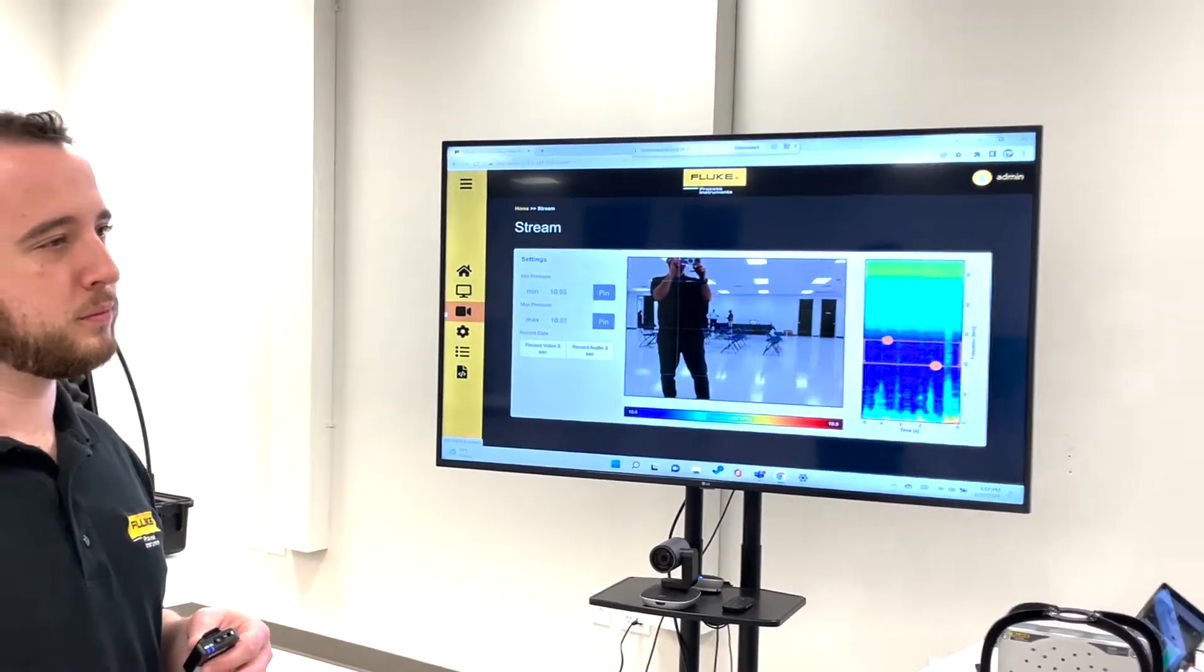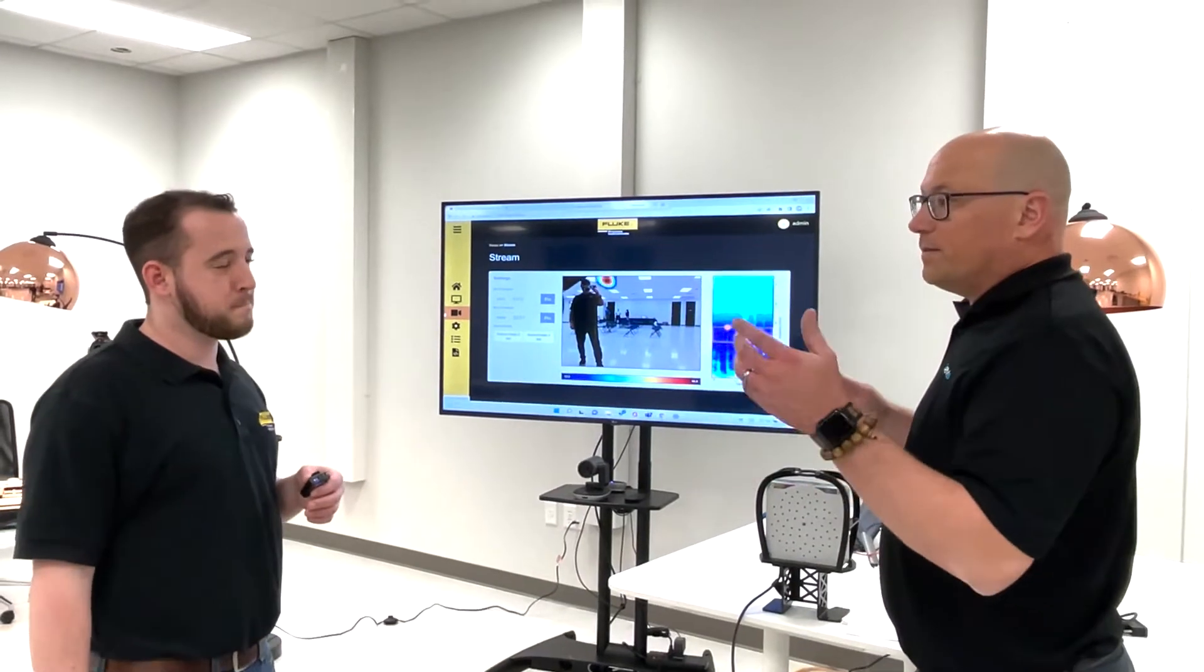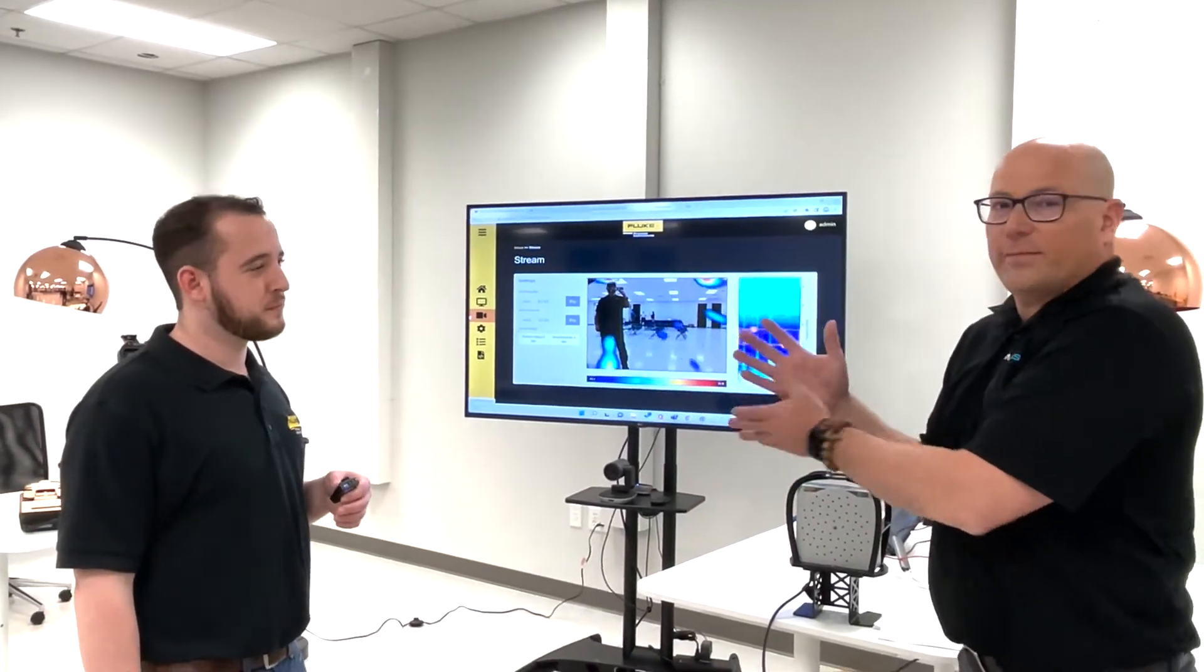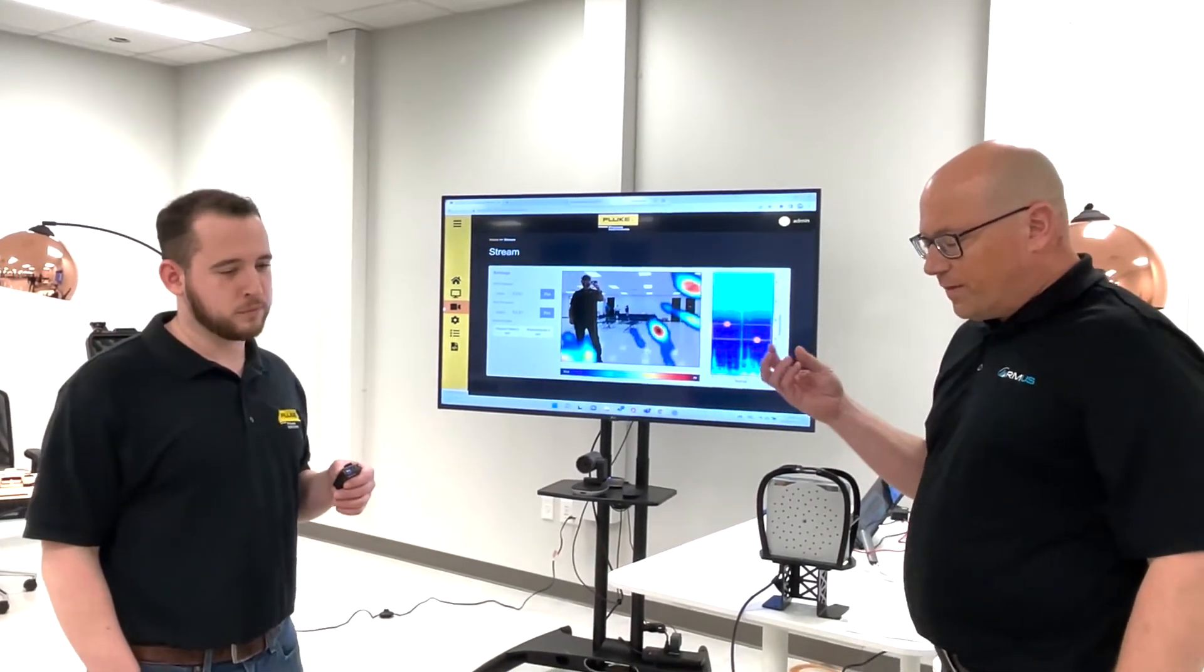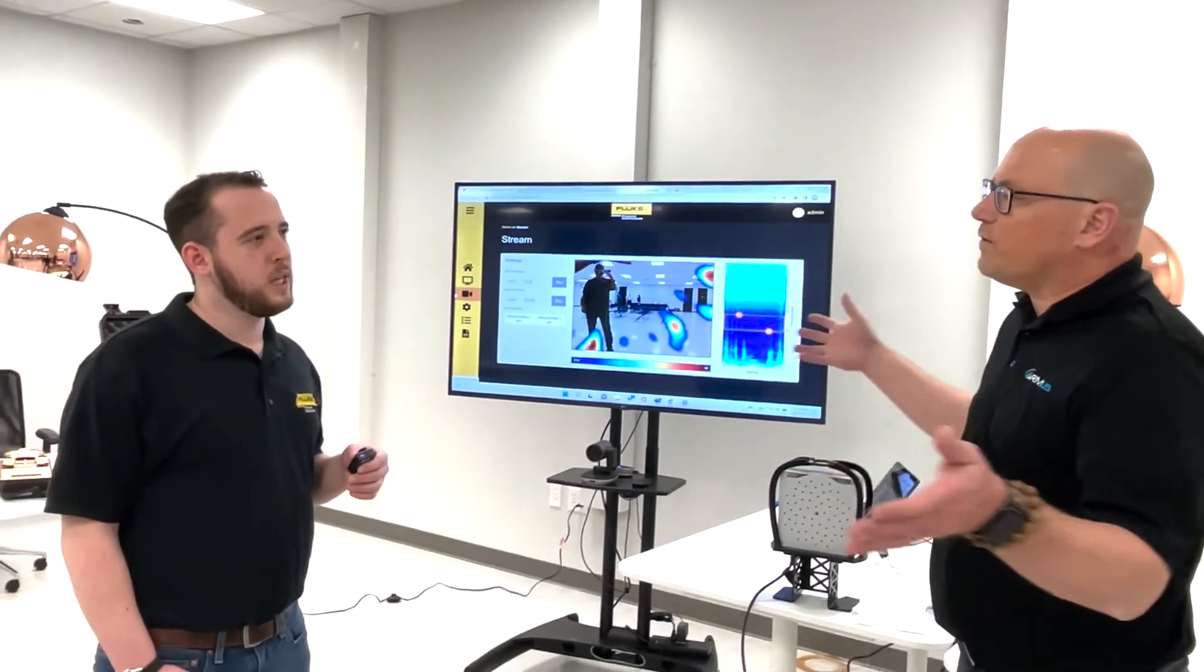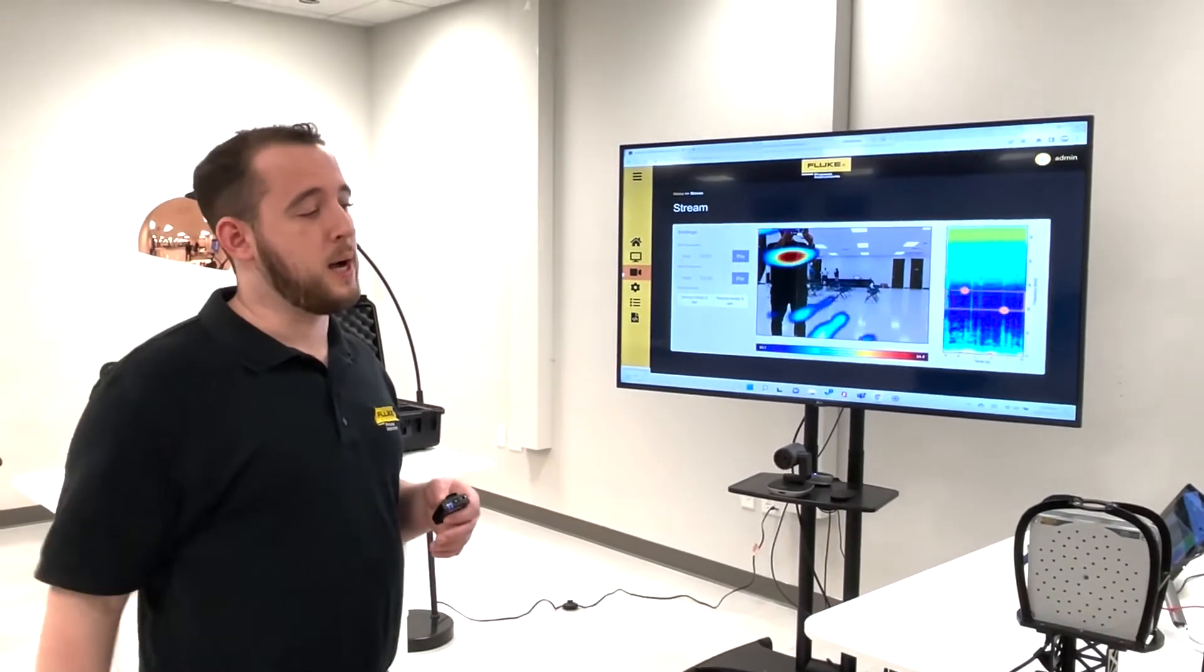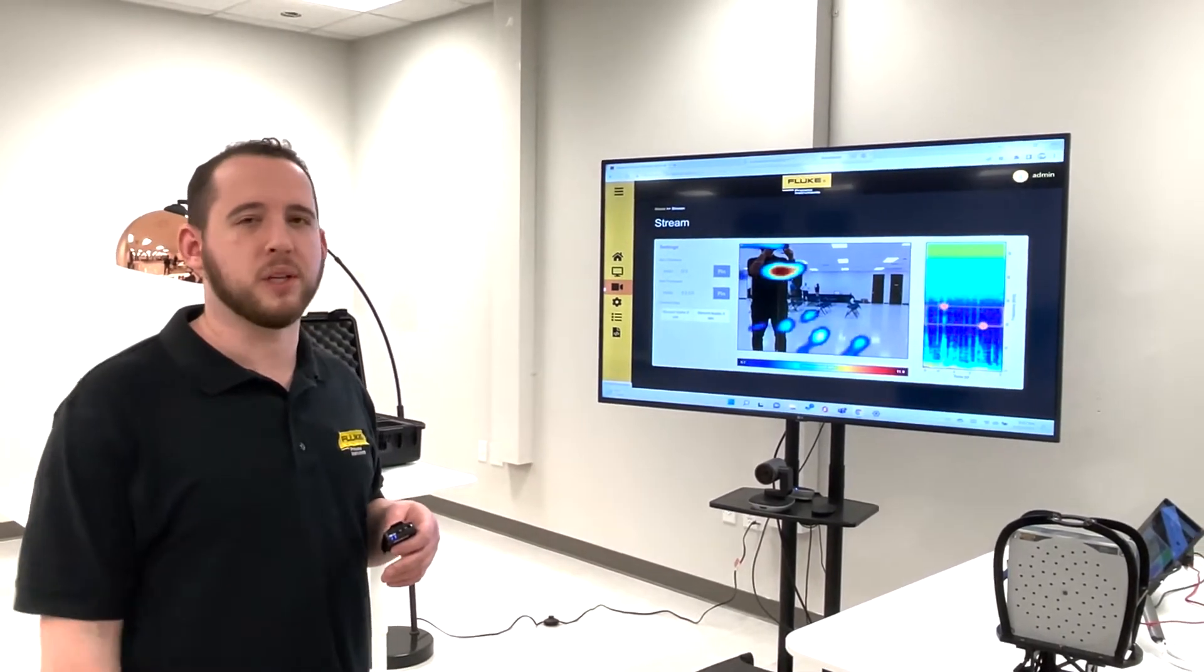Well thanks, Dylan. I have one last question. Range. That's another issue. So this is something we've been testing here. Even putting the sound device behind something, you actually see the sound and it might be being blocked. So you might not be able to see it. But it's very interesting technology that you're at least seeing where the leak might be and then you can go investigate that. So you're honing in on where the issue might be. But what is the range if you're out in the field? Yeah, so it depends a little bit. The primary factor would be how loud the sound is or the leak, how intense. But we'd say around 50 feet kind of best practice rule of thumb as far as what you're able to reliably detect.